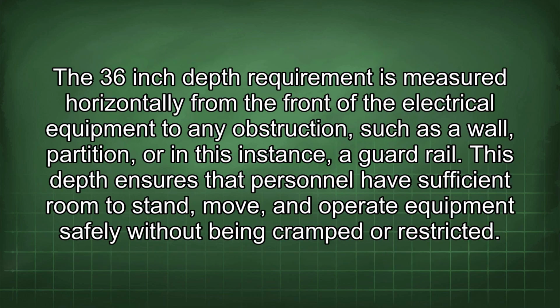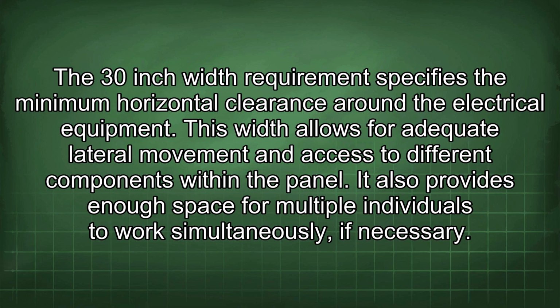The 36-inch depth requirement is measured horizontally from the front of the electrical equipment to any obstruction, such as a wall, partition, or in this instance, a guardrail. This depth ensures that personnel have sufficient room to stand, move, and operate equipment safely without being cramped or restricted. The 30-inch width requirement specifies the minimum horizontal clearance around the electrical equipment. This width allows for adequate lateral movement and access to different components within the panel. It also provides enough space for multiple individuals to work simultaneously if necessary.